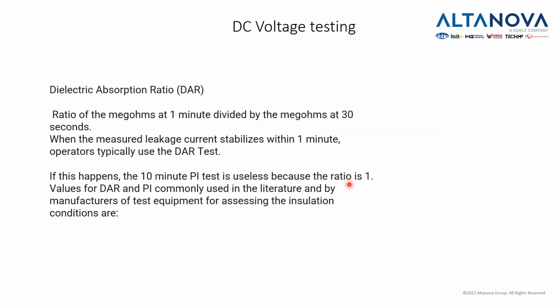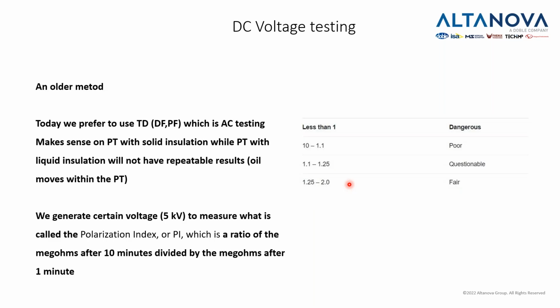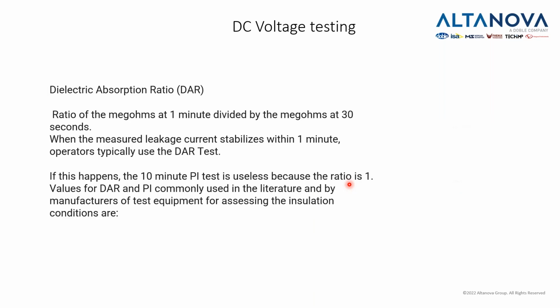Another test, which is called DAR, or dielectric absorption ratio, is almost the same as PI. It's just that the ratio is not 10 minutes versus 1 minute, but it's 1 minute versus 30 seconds. And then we also get the number and compare it to nominal values.